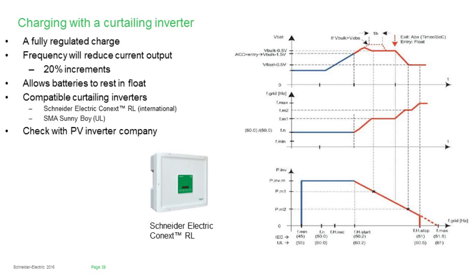So we can send that signal over to the PV inverters, and they'll begin to curtail their power down and allow that system to go into float. Once we've hit float, we can put those batteries into rest, essentially by turning off the PV inverter, because we've created an unqualified source at 60.5 hertz.